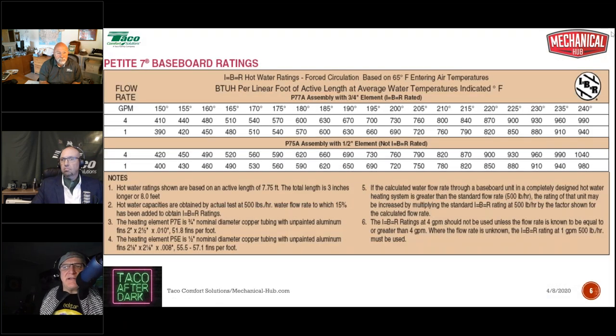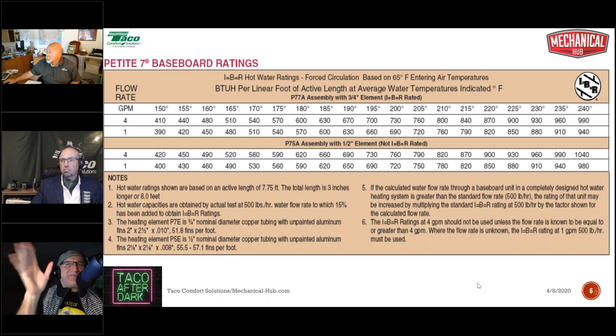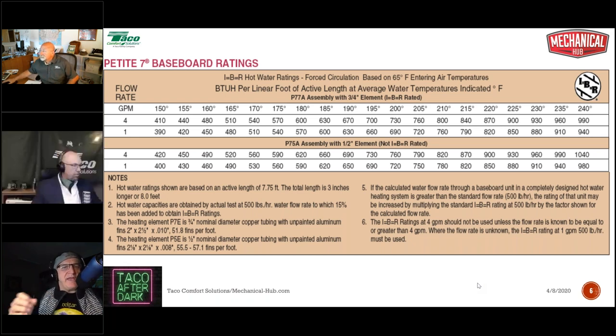What we're looking at right here is a baseboard output ratings chart, and this comes from Sterling. This is their Petite 7 baseboard rating. Now, normally, and type this in if you think, normally everybody goes right to that 550 BTUs per foot or 500 BTUs per foot or whatever it is when they're talking about fin-tube baseboard. And then you say, okay, what water temperature are we talking about? What supply water temperature are we talking about? And the number you're going to get almost immediately is 180 degrees.